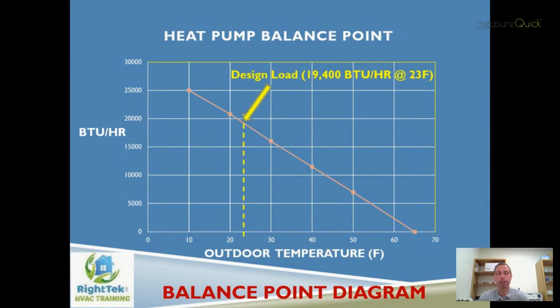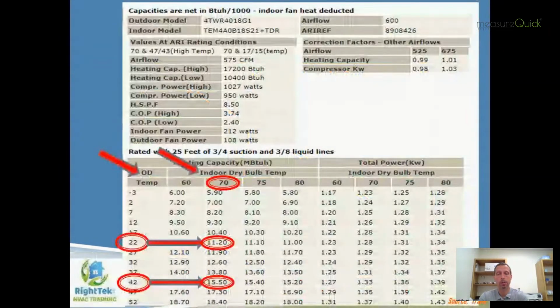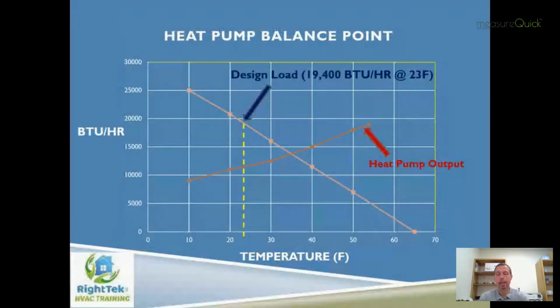Now I can take that performance data that we just looked at, pick a few outdoor temperature data points, and plot that as well. So that dark brown line, you'll notice it starts producing more BTUs per hour at a warmer outdoor temperature, and it decreases as the outdoor temperature decreases. Well, the point is where those two lines cross, where they intersect, at least in theory on paper, is our thermal balance point.